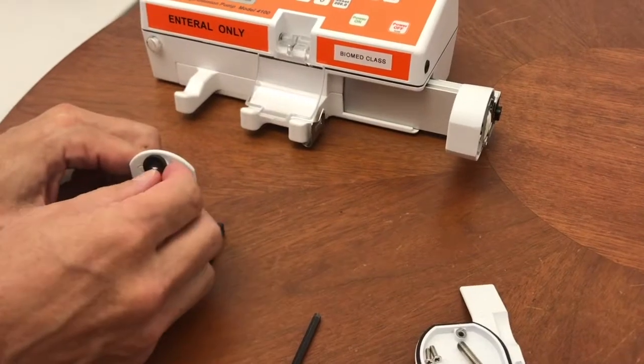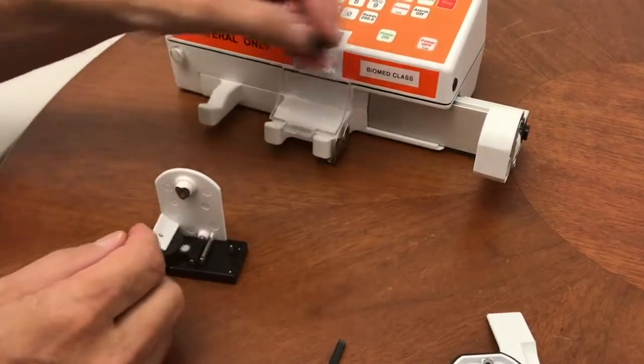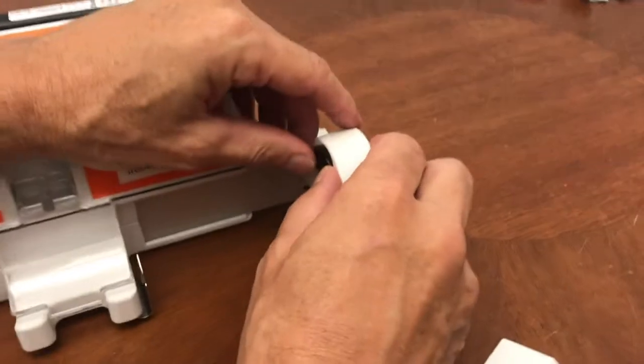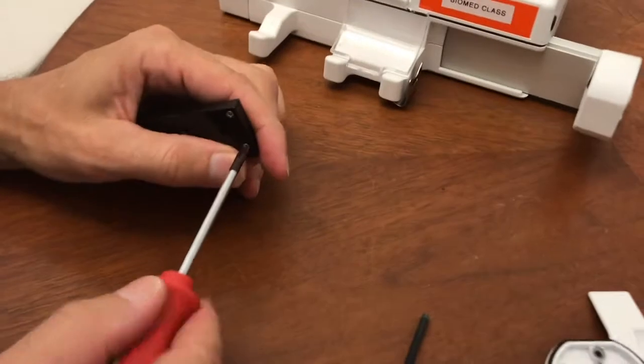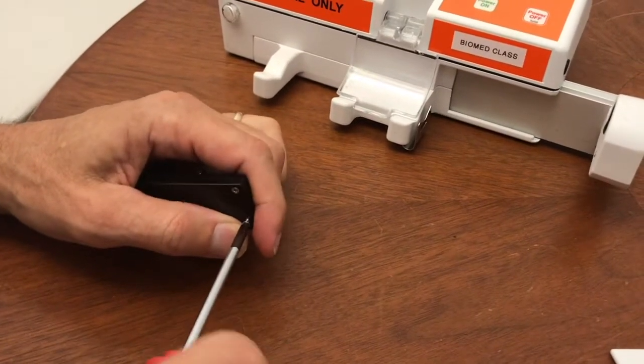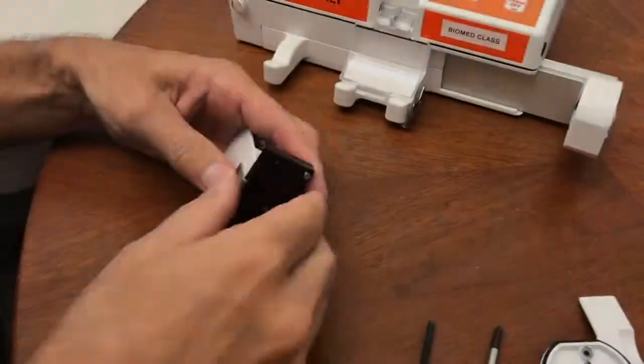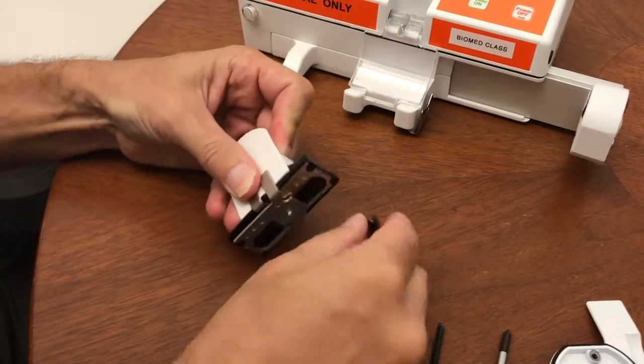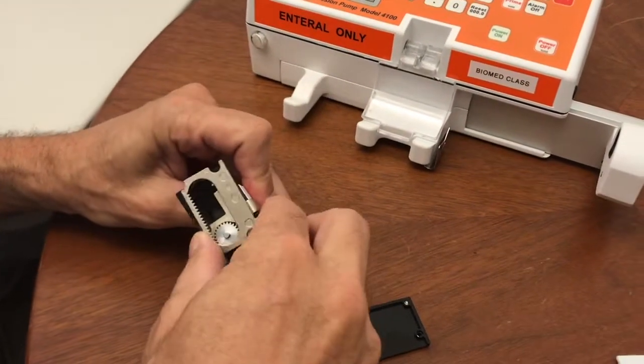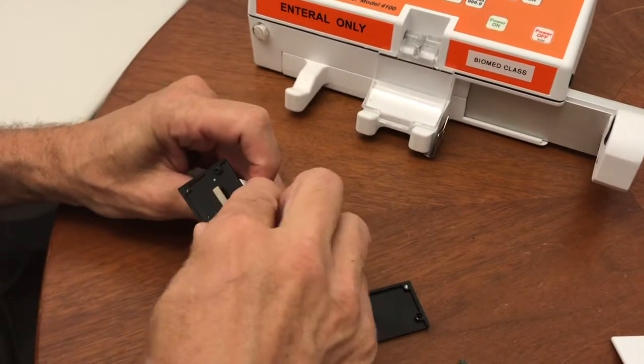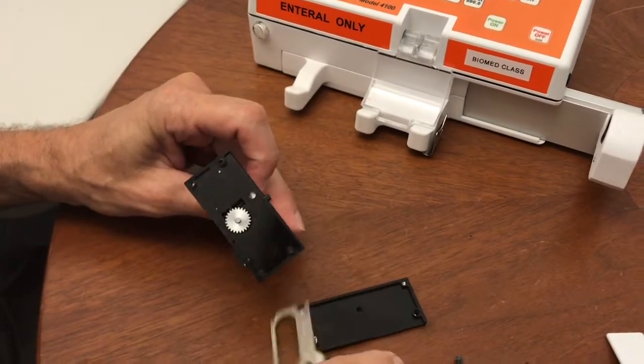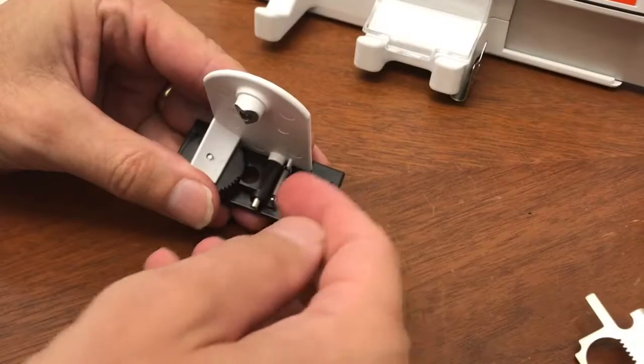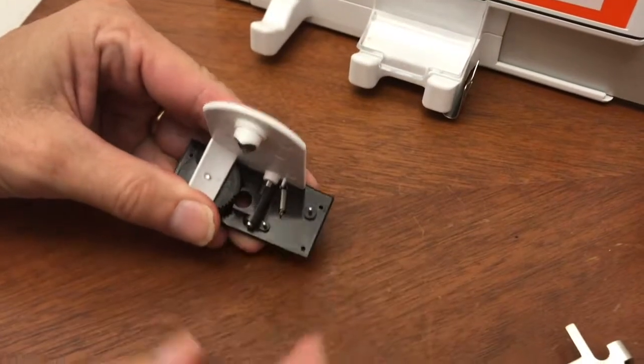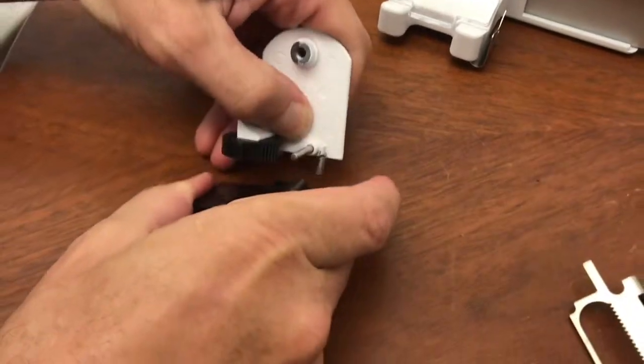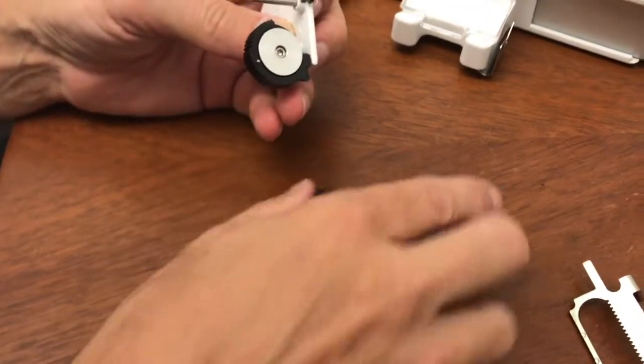The next step, take the transducer seal, remove it from the plate, and just place it into the transducer housing. Then remove the four screws that hold the retainer bottom. Then remove the first retainer bar, second retainer bar, and the gear. The next step, remove the spring from that front pin and then slide the retainer assembly off of the retainer top.